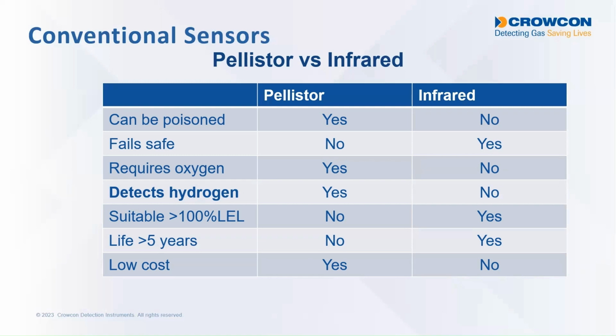So that's the number one problem with pellistors, and silicones are present everywhere all around us. Hand creams, polishes, waxes, greases, they all contain silicones, and any exposure to the pellistor silicon will begin to poison the pellistor. So you can only tell if a pellistor is poisoned by putting test gas on it. That's the only way to tell. So pellistors do need very frequent testing with test gas to ensure that they're still operational. Infrared sensors can't be poisoned, so that's not an issue, and infrared sensors do fail safe. So if the lamp fails or a sensor fails, you do get a fault on the instrument.